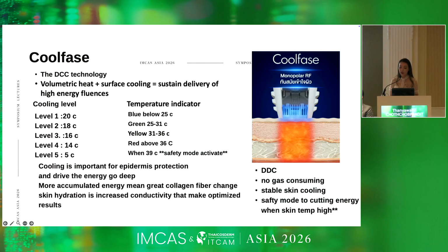One concept I want everyone to remember is cooling controls the depth. Higher cooling levels protect the surface more effectively and drive energy deeper. Therefore, I use a higher cooling level setting for the posterior cheek and deep fiber septa, the anchoring ligament, for the lifting and contouring zone. Lower cooling levels allow more heat to remain superficially. This makes them ideal for periorbital rejuvenation, skin tightening and superficial skin remodeling. In other words, we are not only adjusting the energy, we adjust treatment depth through the cooling setting.